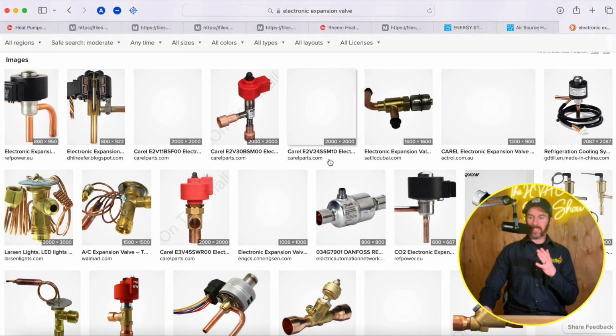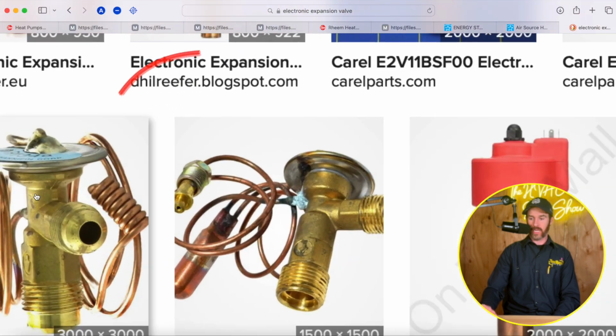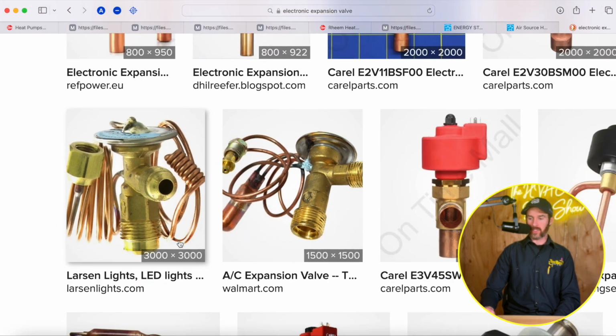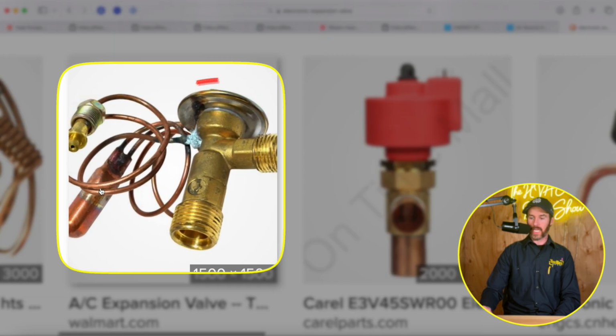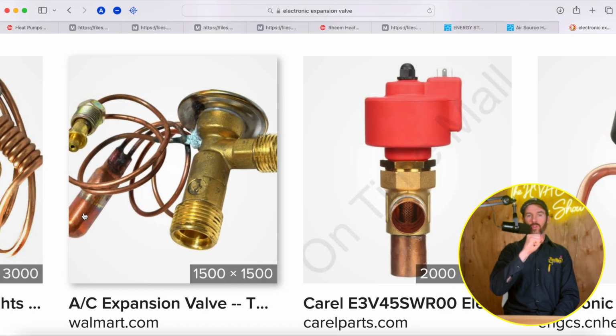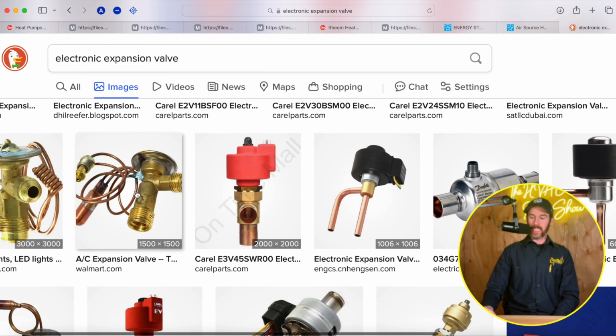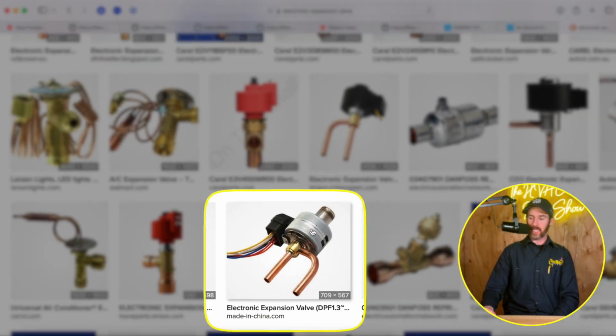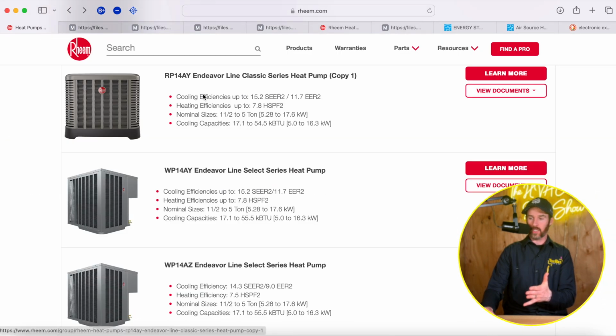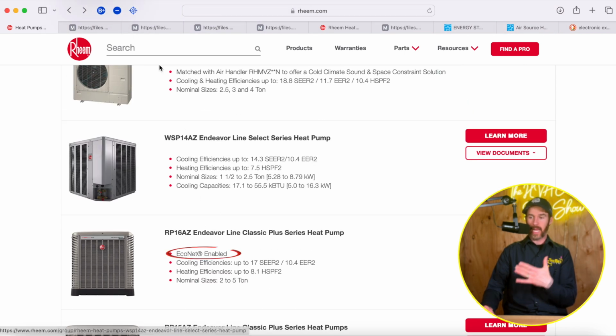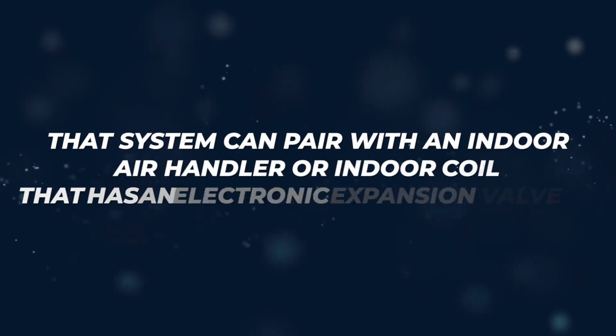Now, this is a picture of a standard TXV, for example, a thermostatic expansion valve. The way that this works is this little bulb right here sits on your suction line, and it opens and closes to allow refrigerant into your coil. But this is just a basic TXV. The benefit of an EXV, an electronic expansion valve, is that it is a communicating system. So when we looked at some of these systems earlier, and you see terminology like EcoNet enabled or communicating systems, that means that system can pair with an indoor air handler or indoor coil that has an electronic expansion valve. The benefit is that when that system first kicks on, it opens and closes, allowing a precise amount of refrigerant into your indoor coil.